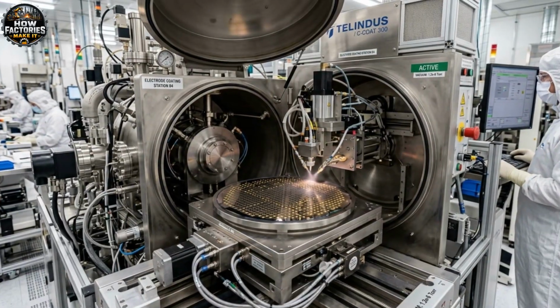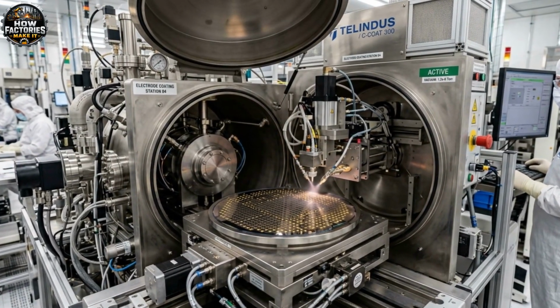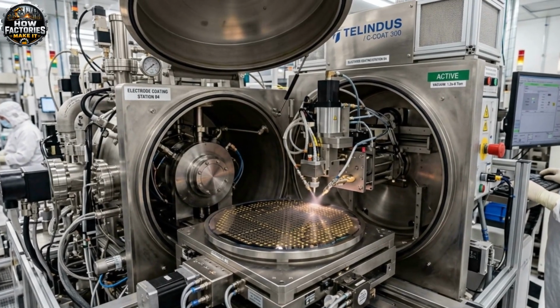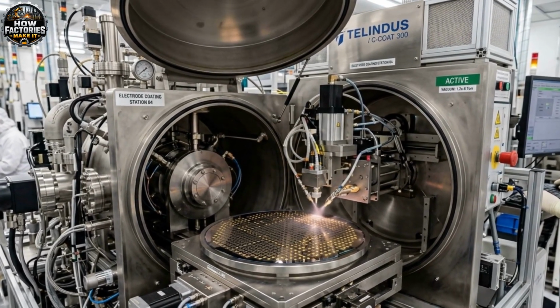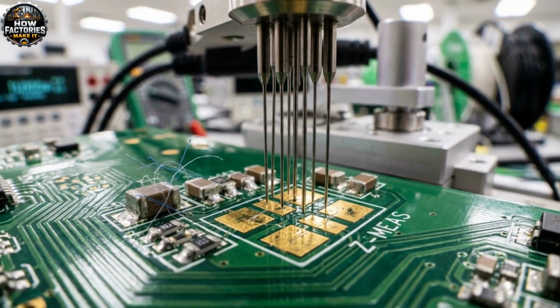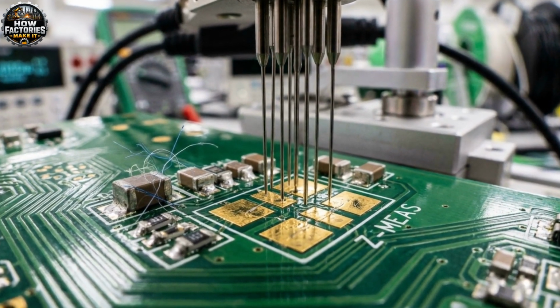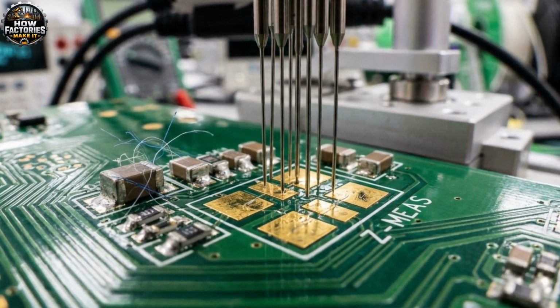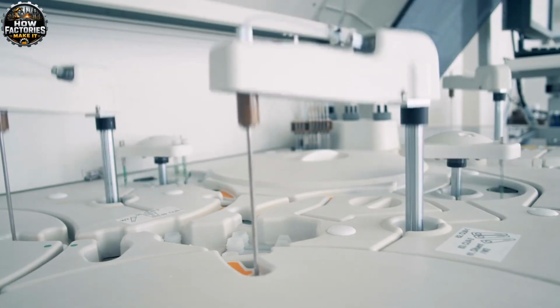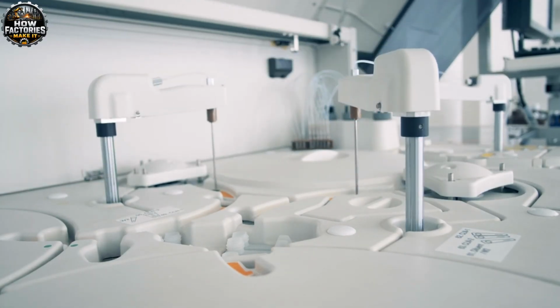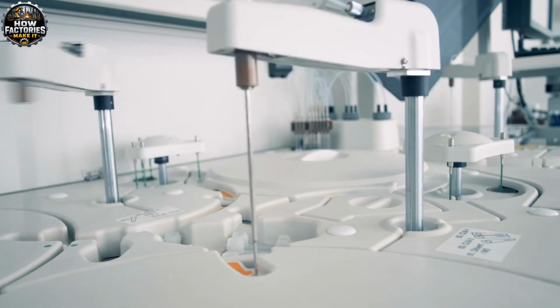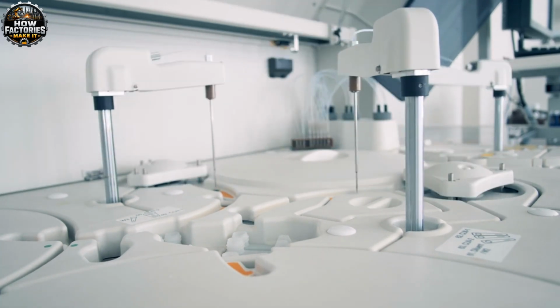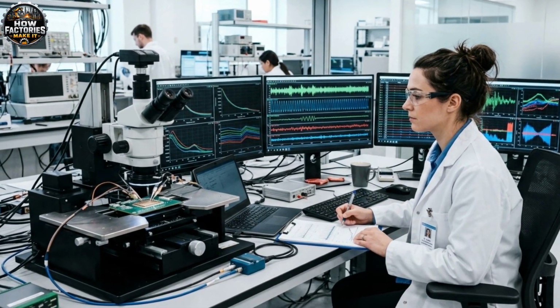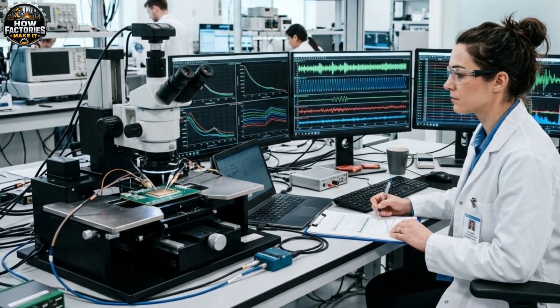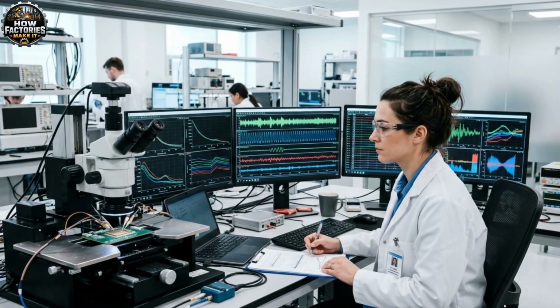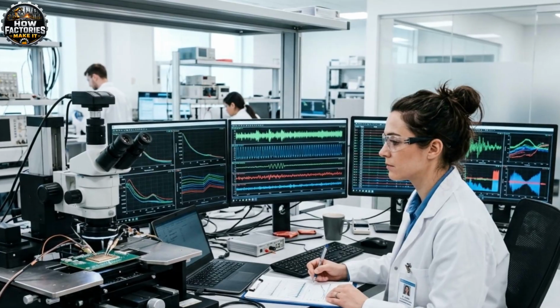The wafer is placed inside controlled processing equipment, where the coating is deposited only on the required electrode sites. After treatment, automated probe systems test the electrical impedance of every electrode. Electrodes outside the permitted range may indicate contamination, a broken conductor, or an incomplete coating. A single defective connection could remove an entire recording channel. Therefore, inspection must happen repeatedly throughout production.